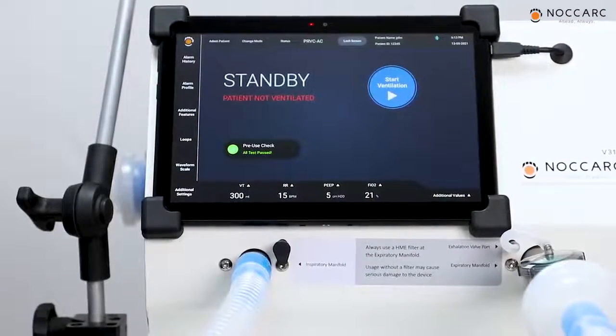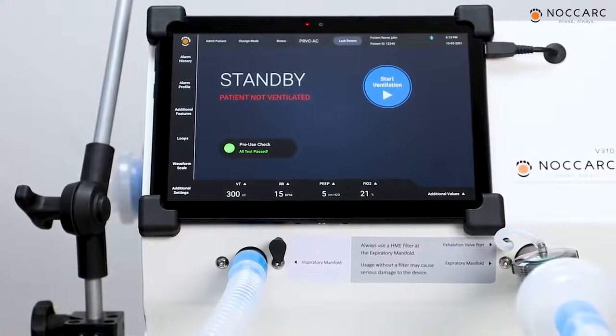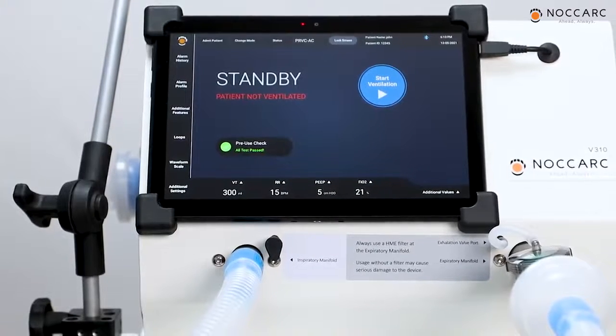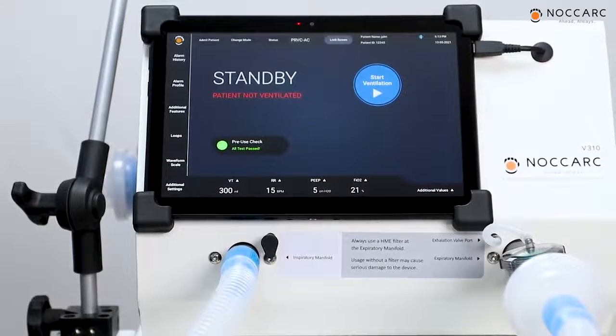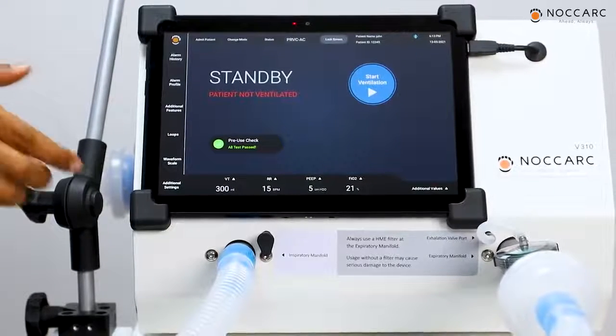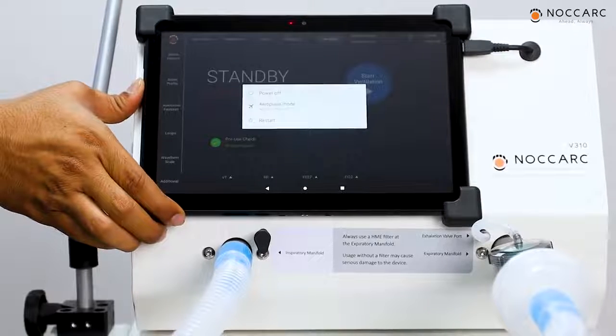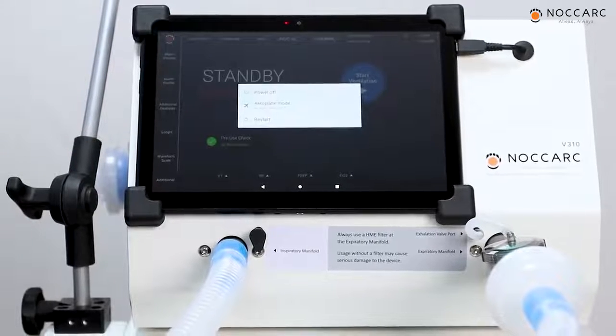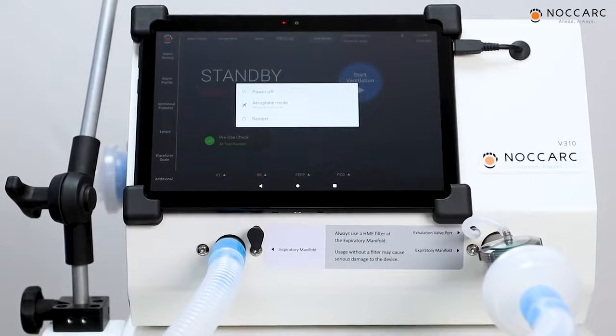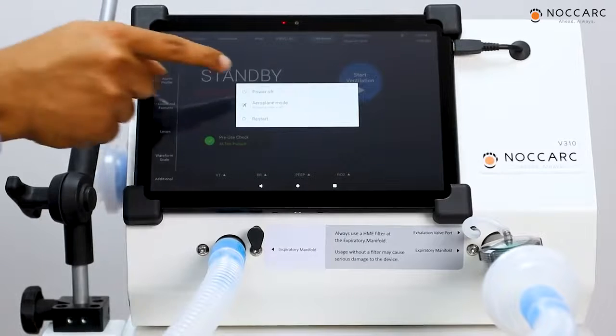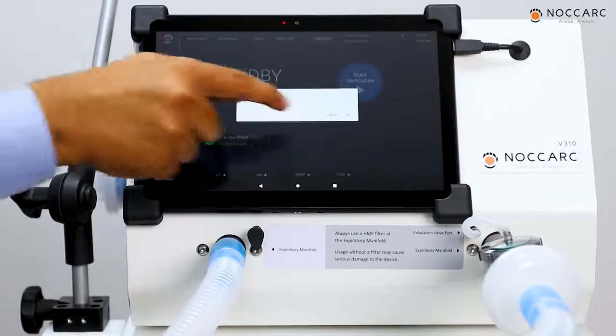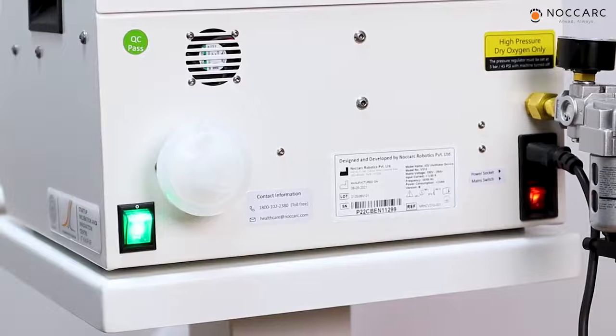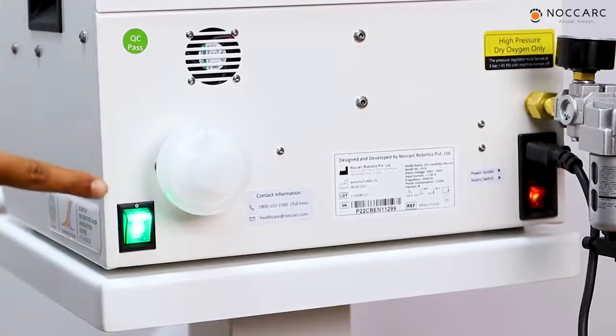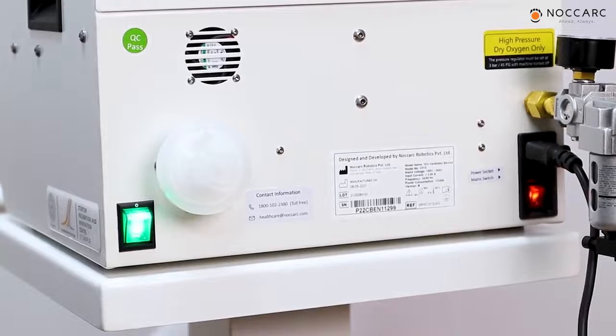When user wants to keep V310 on standby, always ensure the display is turned off. To turn off the display, press and hold on the display button provided at right side of the screen. One prompt will appear on the screen. Press on power off, press on OK. For normal operation of Noccarc V310, ventilator switch should be in switch on condition.